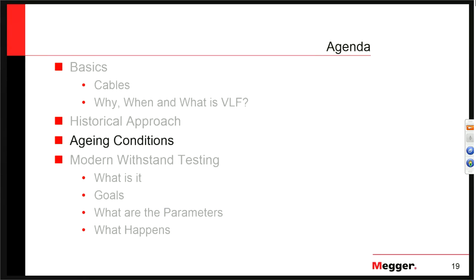Q&A: When would you select VLF testing instead of DC HIPOT for medium voltage? Basically, for medium voltage cables, the only time DC is still acceptable is for PILC cables — it's the only time IEEE has a standard for it. If you're testing EPR or XLPE, you really want to be using VLF. Other than that, maybe there are practical considerations like only having a DC test set available, but as far as standards go, you're looking at VLF.